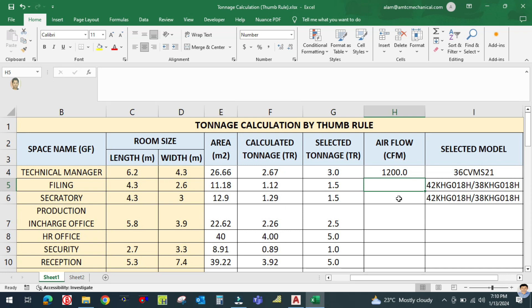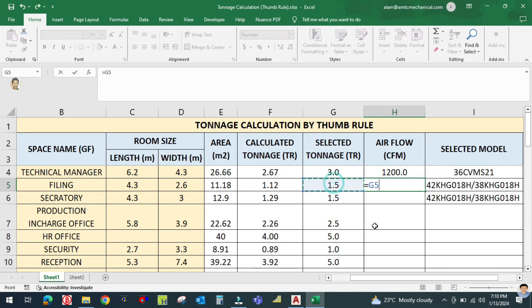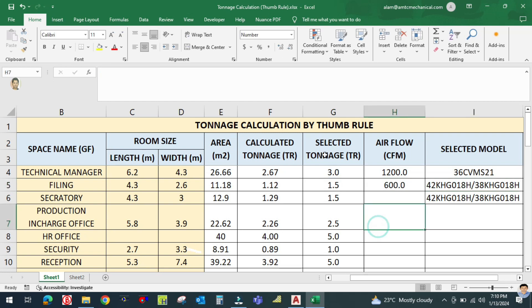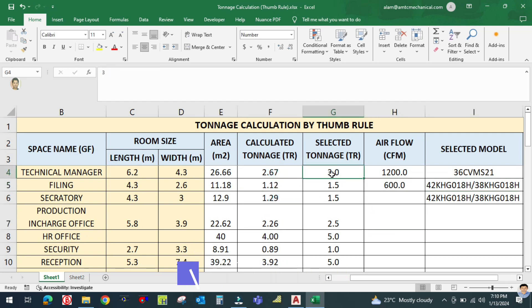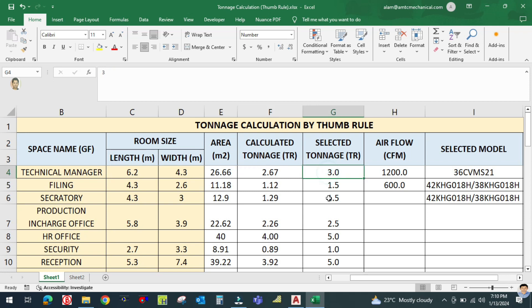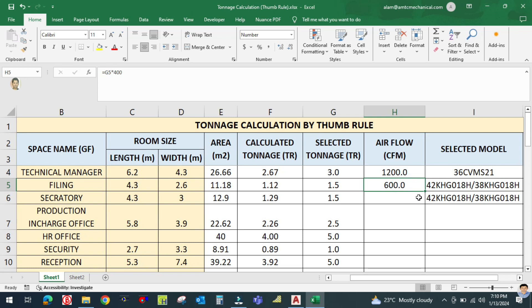For example, 1.5 tons multiplied by 400 gives the calculated CFM. This is the calculated ton value, and this is the selected ton — because the calculated number is uneven, we use the roundup value, which is the higher one. So this is the selected tons and this is the airflow.